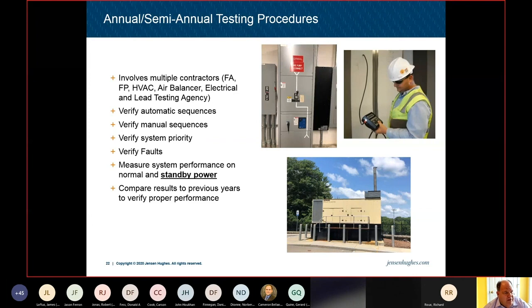One of the pictures in the upper left-hand side is the fire pump disconnect switch. A lot of times the fire pump is wired ahead of the main disconnect for the building. So to truly drop building power, you have to drop two things: the fire pump main disconnect and the main building disconnect. That's why we need the electricians involved, so we can drop power to the entire building. So our overall system, fire alarm, sprinkler, fire pump, smoke control, everything's running on normal power. Then we dump the normal power and the standby power to the building completely to verify that the emergency generator turns on and the automatic transfer switches switch over to re-engage all those various systems, the fire alarm, the fire pump, the smoke control system. All of that is now getting fed from the emergency power. So it's an involved test.